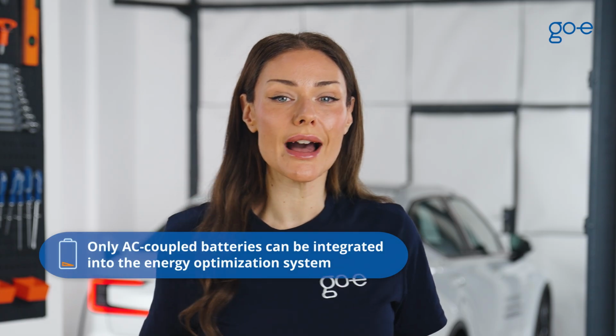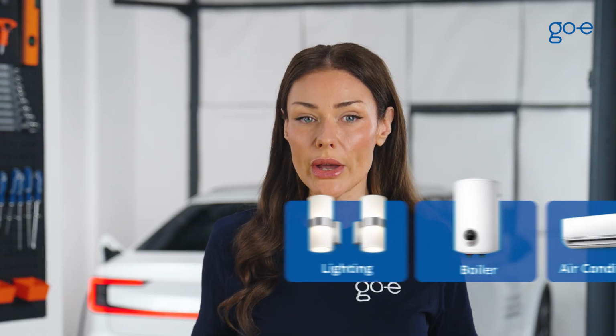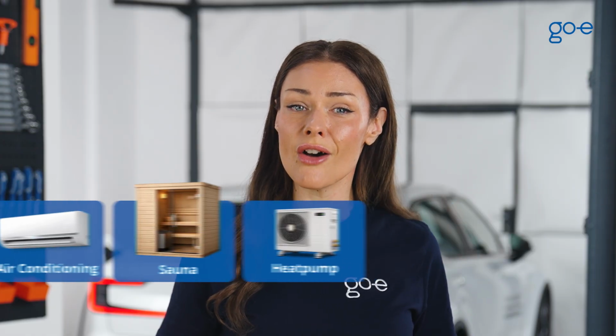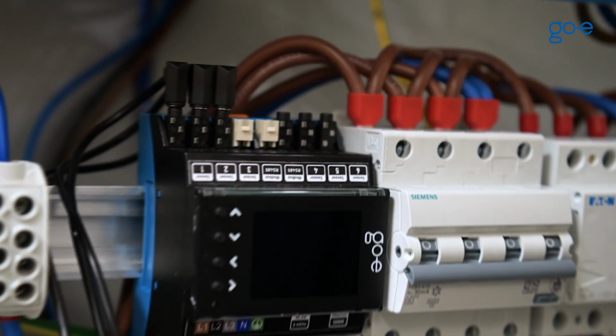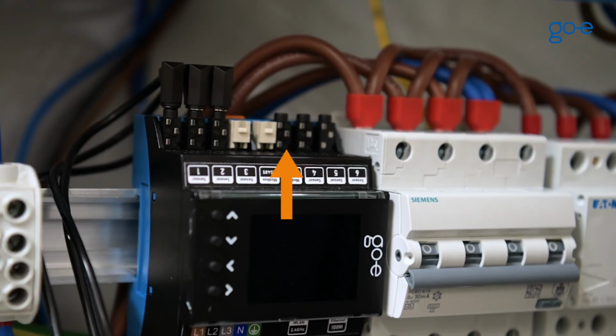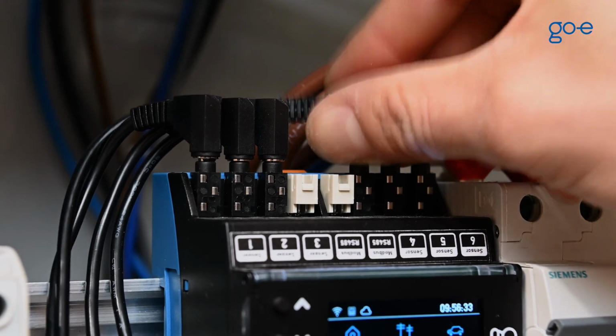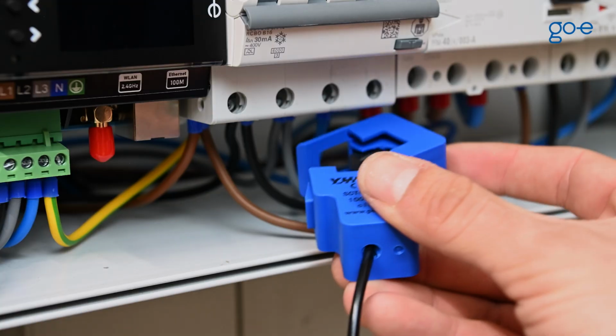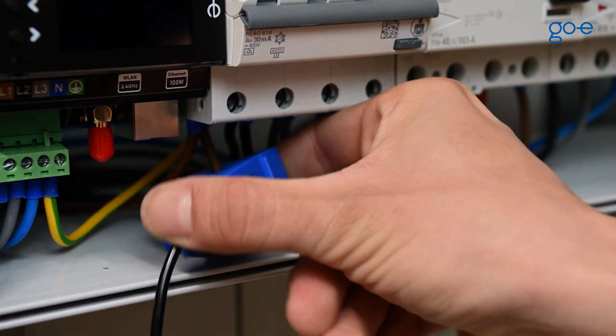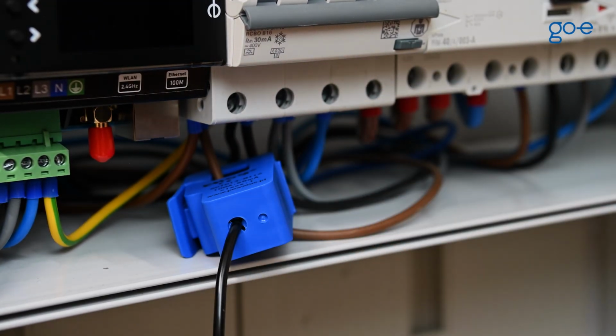You can also use the current transformers to measure the consumption of individual circuits, such as lighting, a boiler, air conditioning, a sauna, or a heat pump. Now, plug the jack plug of a current transformer into one of the remaining current measurement inputs labeled sensor. You can assign them freely. For example, let's use sensor connection number 4. Clip the current transformer around one phase of the device or circuit, the current of which you want to measure.